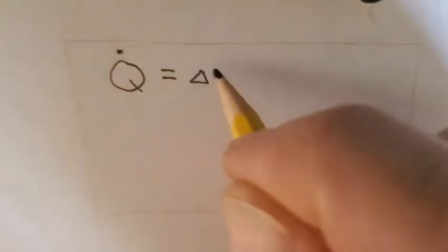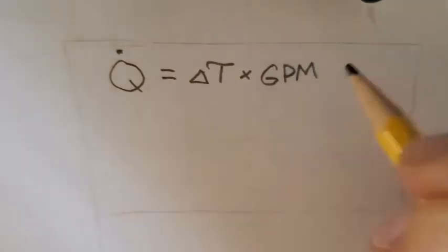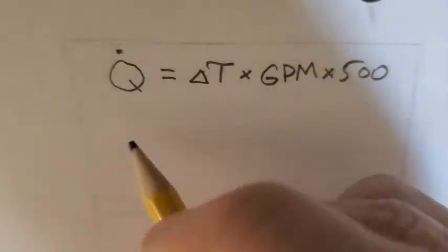Using the simple equation, rate of heat transfer, or Q, equals delta T times GPM times 500.